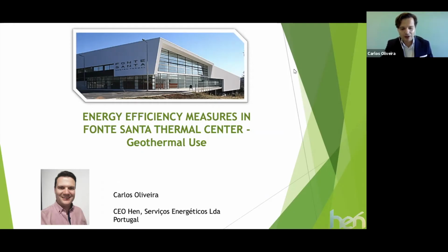I'm going to give a short introduction about geothermal heat pumps. They are able to extract the energy accumulated in the soil and in the groundwater, and conduct that thermal energy into the building. The water temperature in the subsoil at depth is stable, so we can extract all the energy, and the COP, the coefficient of performance, is stable — one of the advantages of these products. We can produce both heat and cold.